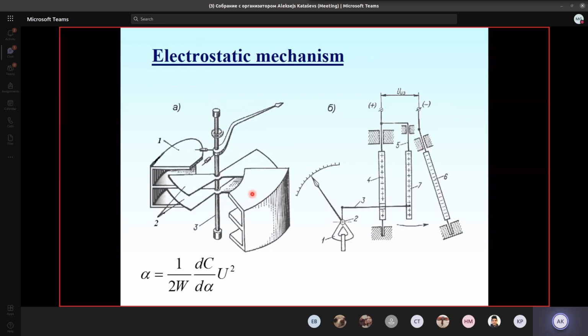Compared to all other mechanisms, electrostatic is one of the less sensitive. It actually starts to work from a voltage of more than 10 volts, and even more than 50 volts. But it may be used to measure AC voltage too, because the deflection of the index is proportional to the square of the voltage.